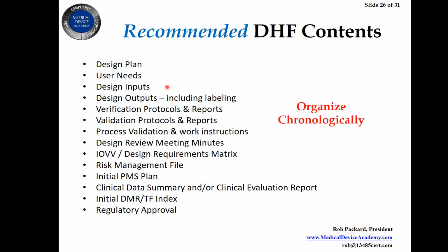Slide 26, we have a recommended DHF contents. So this is recommended. It's not required. There's no place where it says what you need in it. All they say is you need all the records according to your design plan. So the design plan's got to be in there. It might not be a bad idea to include a copy of your procedure in there as well. I don't have that on that list, but it's a very good idea because they always ask for that, and it's kind of nice to have the design procedure, at least the revision of it that was used for that design project, actually in the file, whether it's virtual or physical.